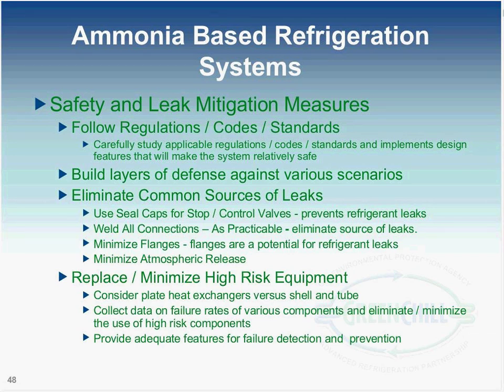The systems would have such a low amount of charge. As you heard Bruce mention, a typical conventional refrigeration system in a store would hold 3,000 to 4,000 pounds of refrigerant. And when you go into an indirect system such as glycol or CO2, even when you use the platinum level certification, the charge of the refrigerant goes into hundreds. It could be 200, 300 pounds.